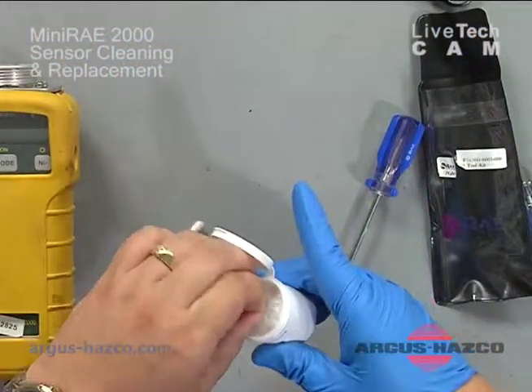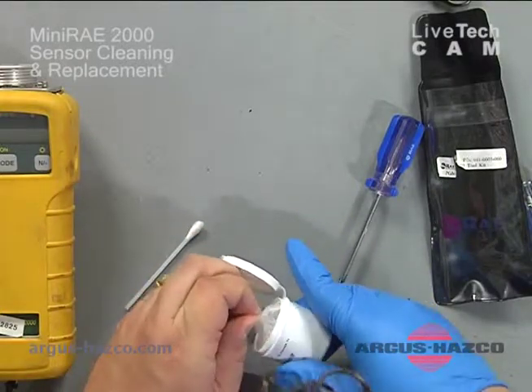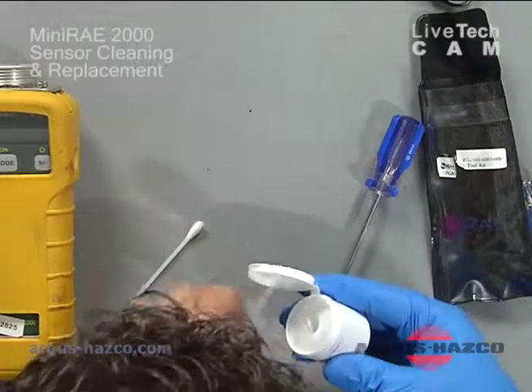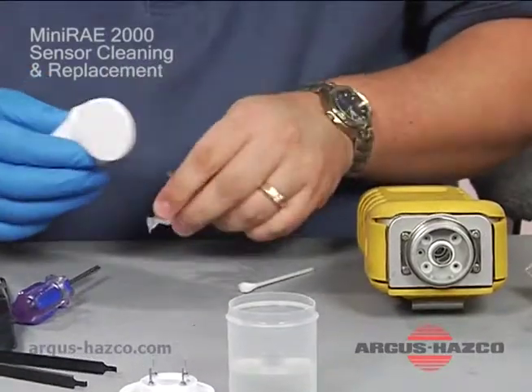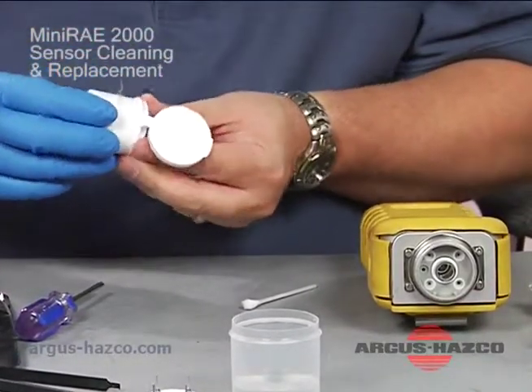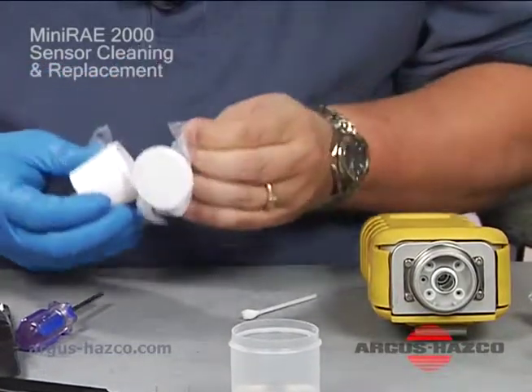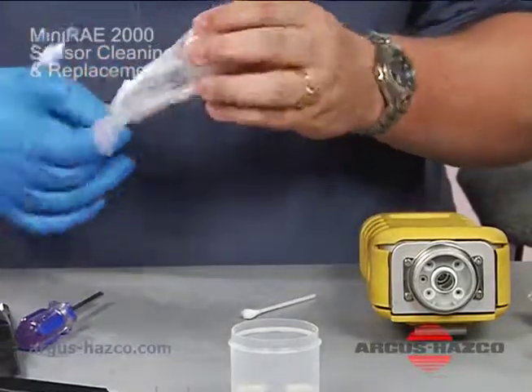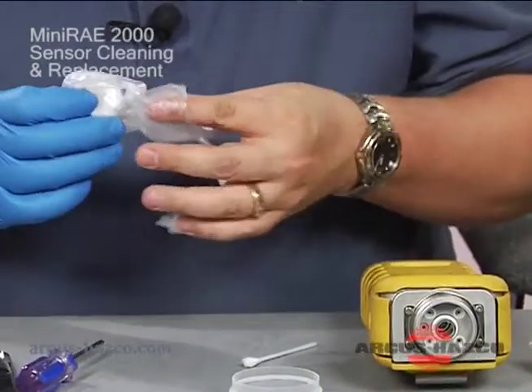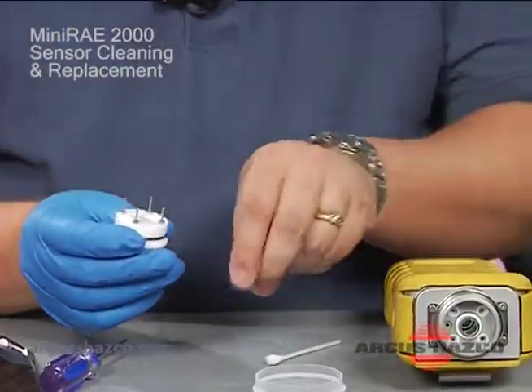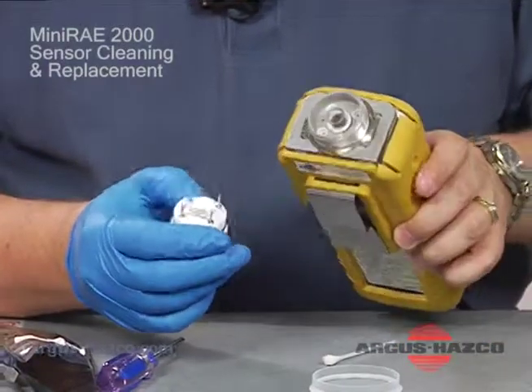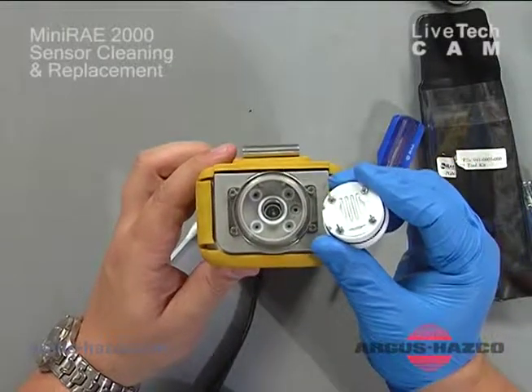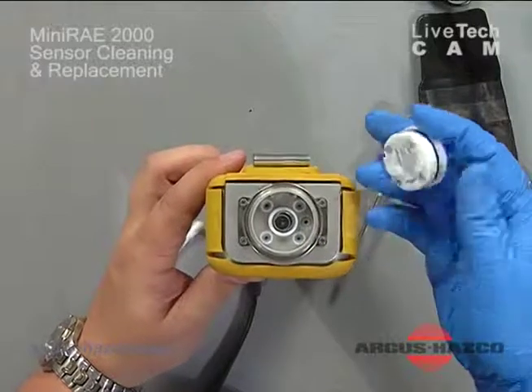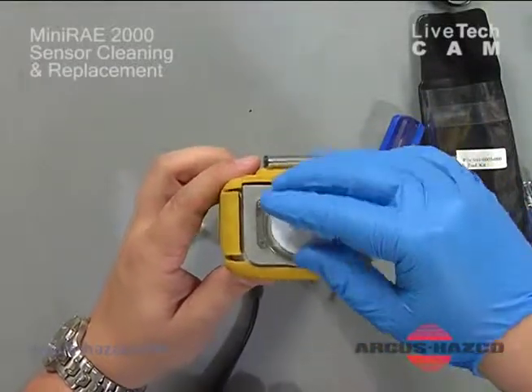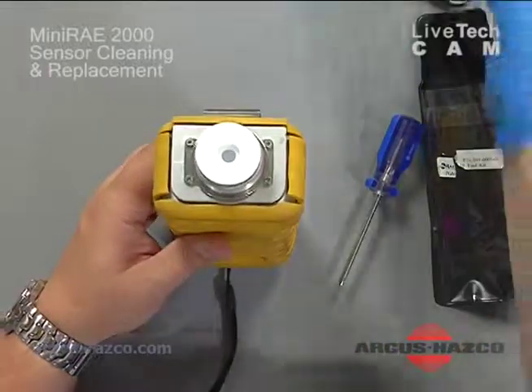Once the lamp has been dried and cleaned, this will be the same as replacing the sensor. You grab the new sensor, and again, lining it up over the lamp, you'll see a larger prong off of the sensor that lines up with the larger socket down in there. You simply line it up, push down, not too much, as it will self-align once you re-establish the probe.